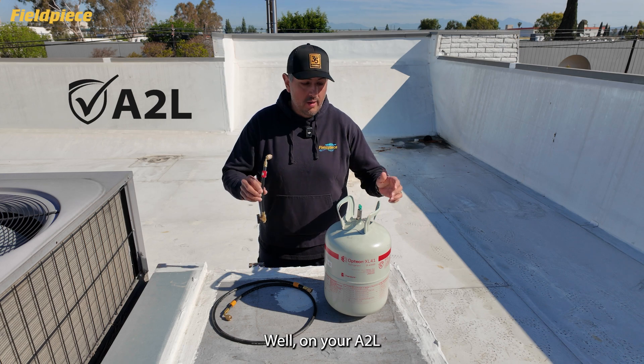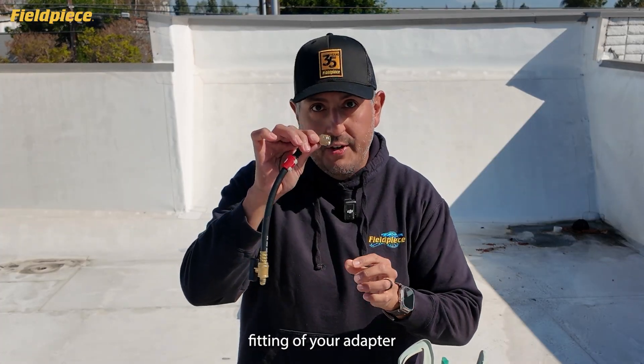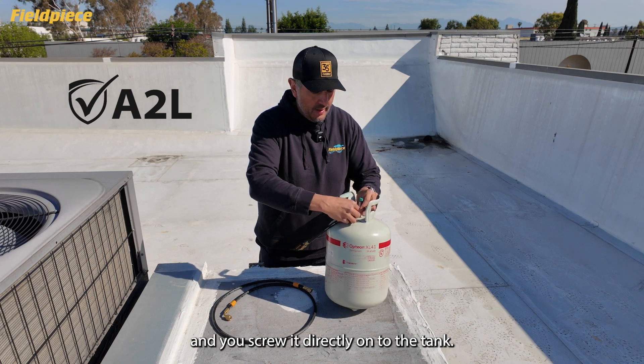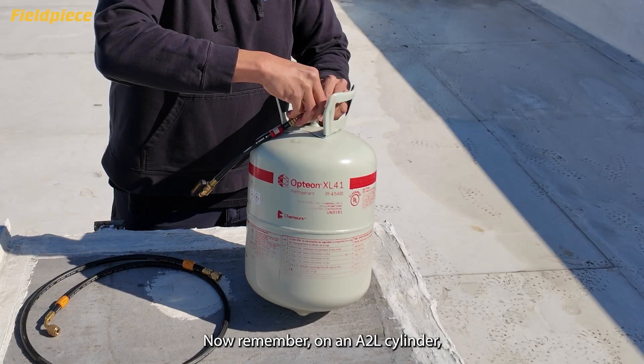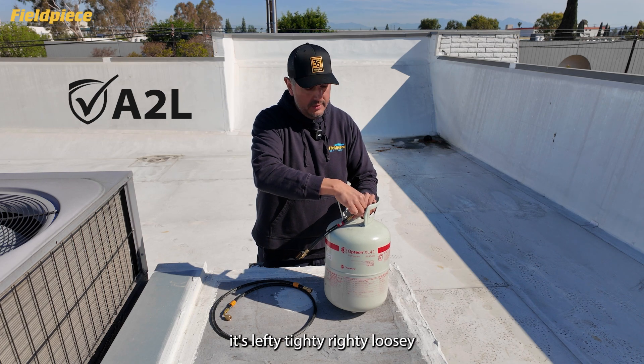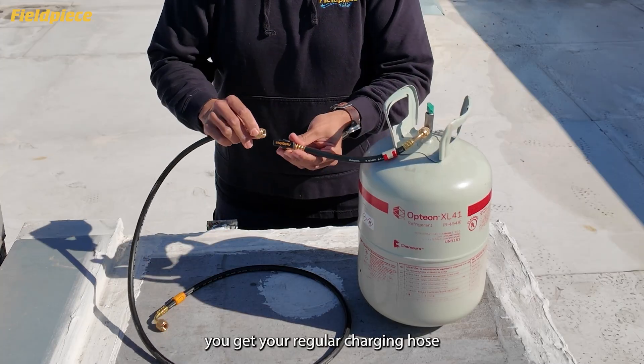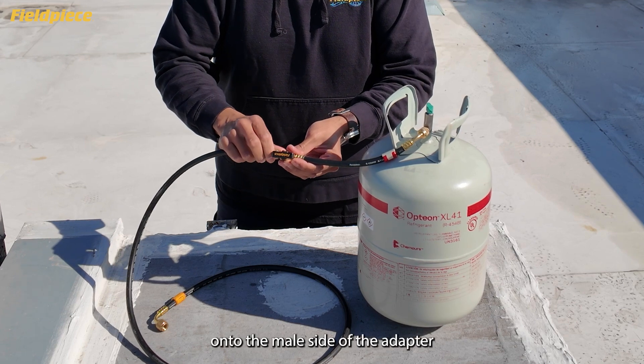How do you use it? On your A2L tank with the reverse threading, take the female fitting of your adapter and screw it directly onto the tank. Remember, on an A2L cylinder, it's lefty-tighty, righty-loosey. Once that's installed, take your regular charging hose and screw it onto the male side of the adapter. And you're ready to go to charge the system.